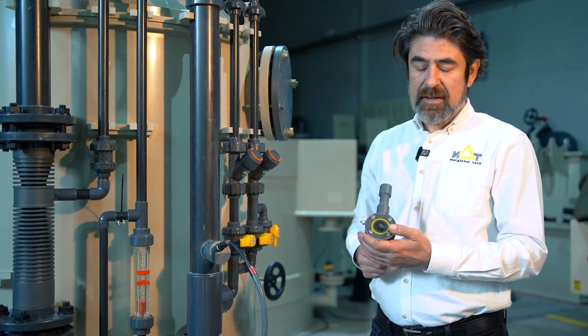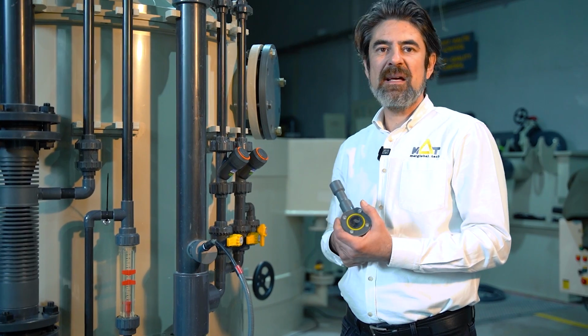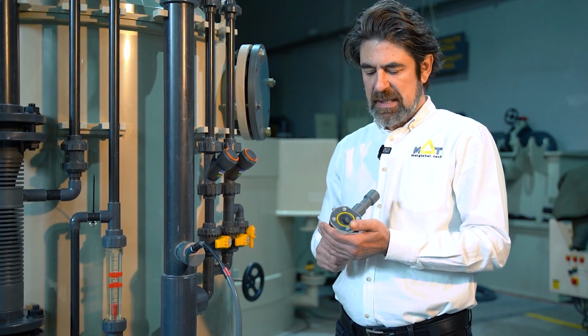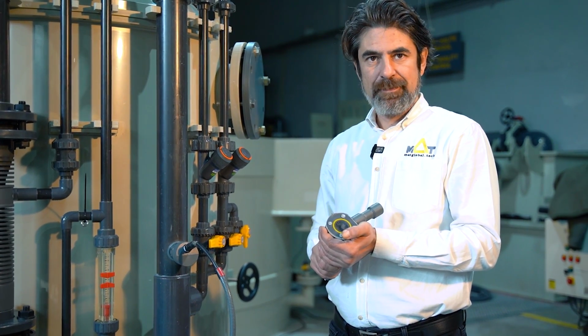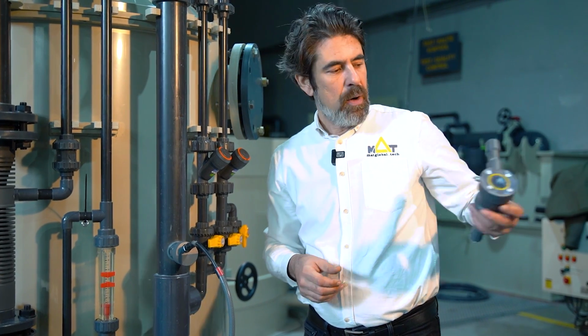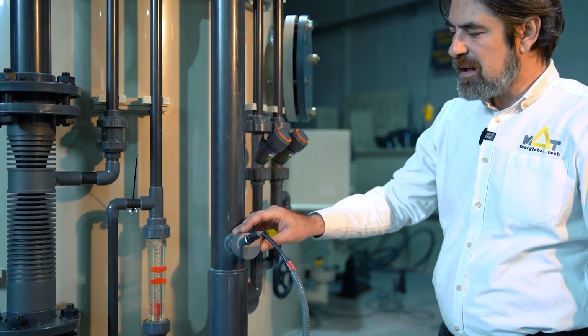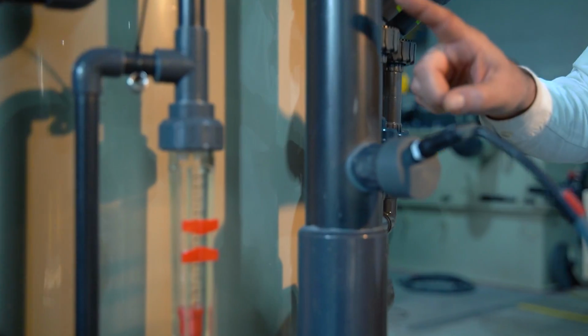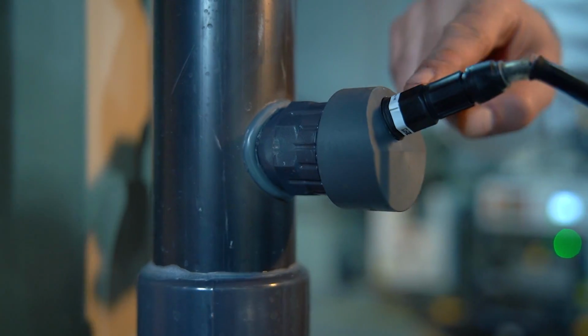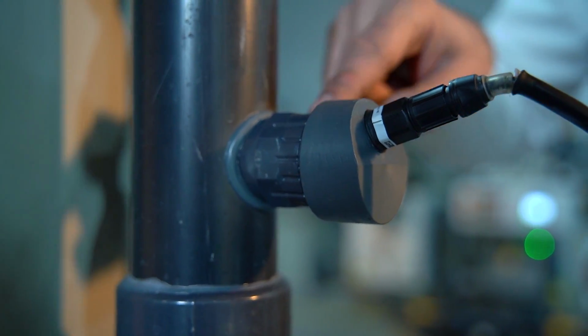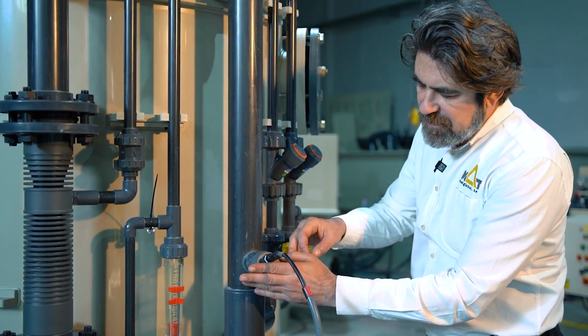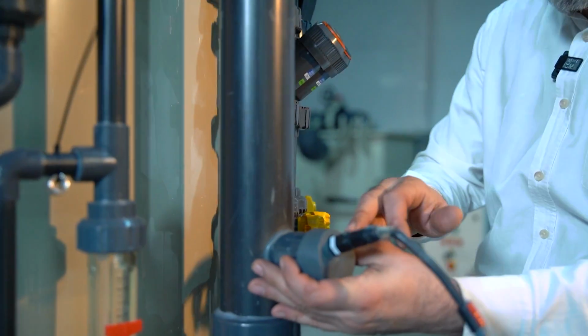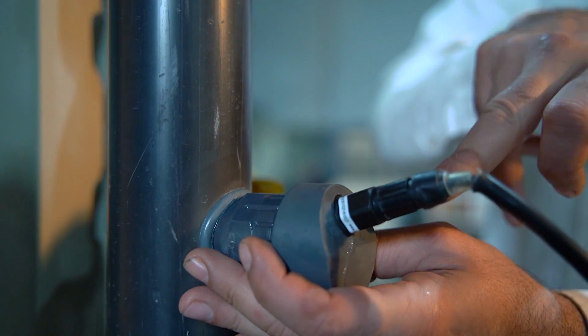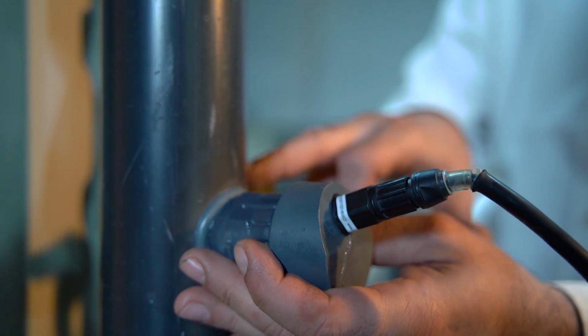And the second unit I will explain is a dry tap unit, as we call it. It's a service probe connection. First, let's see how we are using the conventional standard inline connections. So, for example, this is a protein skimmer, and now we are using an ORP probe here. Now I will show you the disadvantage of a standard inline probe connection. So this one is simply inserted into a pipeline as in common use.